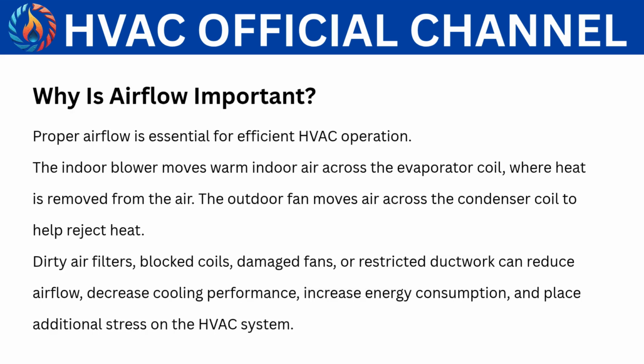Why is airflow important? Proper airflow is essential for efficient HVAC operation. The indoor blower moves warm indoor air across the evaporator coil, where heat is removed from the air. The outdoor fan moves air across the condenser coil to help reject heat. Dirty air filters, blocked coils, damaged fans, or restricted ductwork can reduce airflow, decrease cooling performance, increase energy consumption, and place additional stress on the HVAC system.